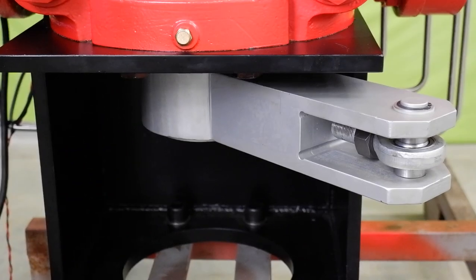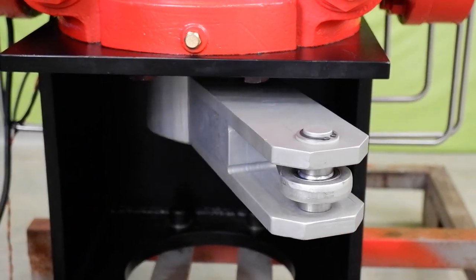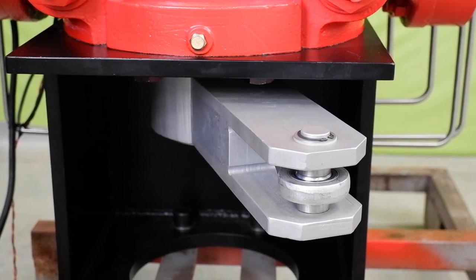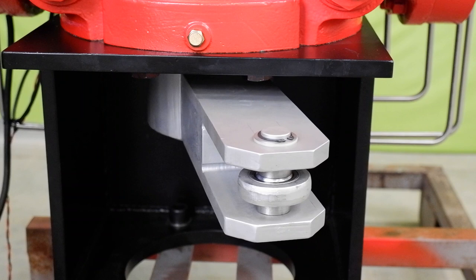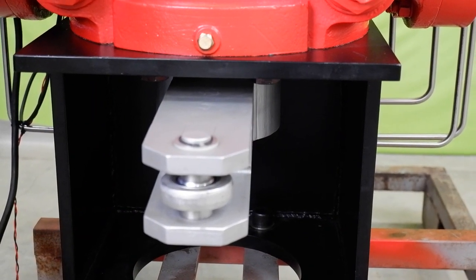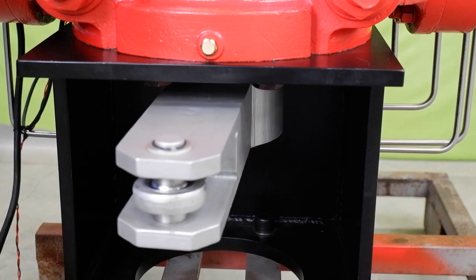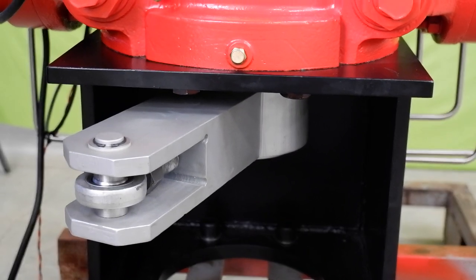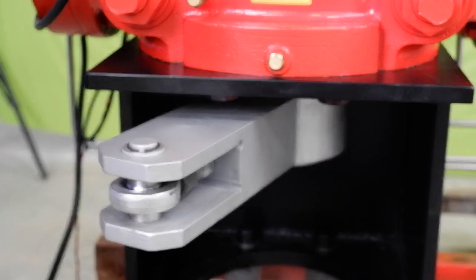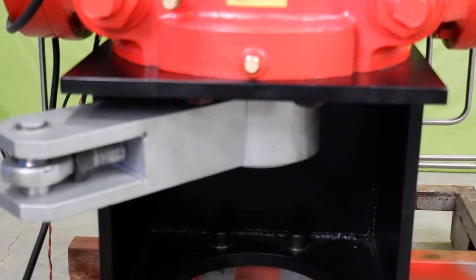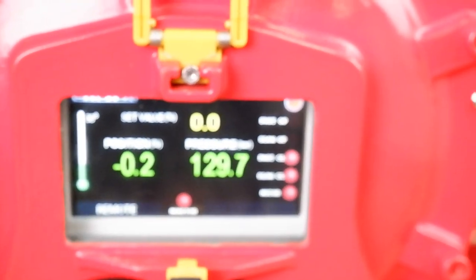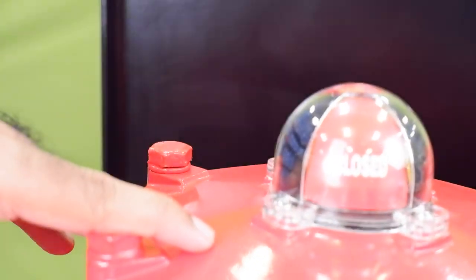Now I will close the valve remotely in the same way. Now the valve is closing, at 75%. Now closed to 50%. Now closed to 25%. And now the valve is fully closed to 0%, and it is shown in the TFT display and on the mechanical indication also.